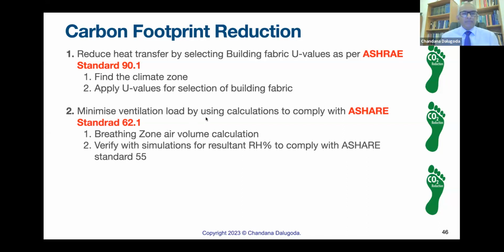energy. So what we do over and above, verify with simulations the resultant RH of the design, whether it complies with ASHRAE standard 55. It says relative humidity inside the air-conditioned building should be below 60%. So we keep it at 55 to 60%. If the relative humidity is above 60%, how do we find this? From the simulations. We'll have to take evasive action to reduce relative humidity below 60.